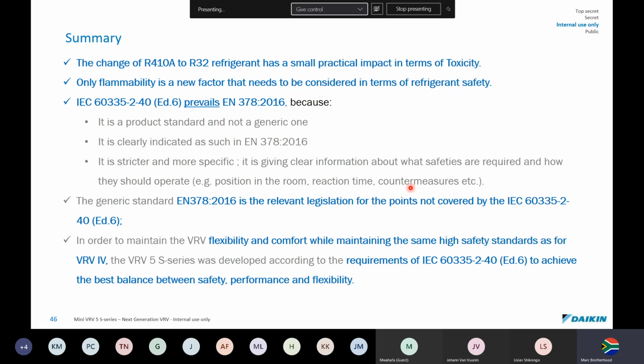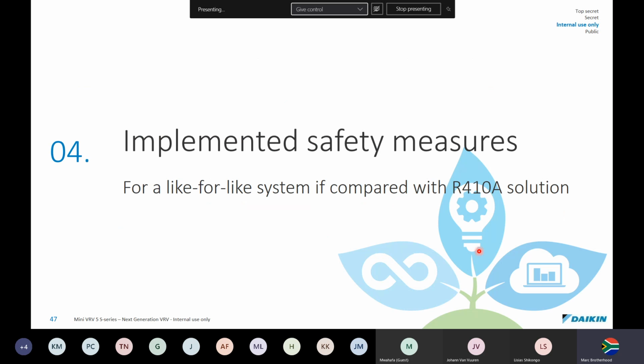Daikin use IEC standard 60335 because it's a lot stricter than 378. And in order to maintain the VRV flexibility and comfort while maintaining the same high safety standards as for VRV4, the VRV5 series was developed to the requirements of these standards. So they like to sort of brag about the standards that they've added. Importantly, because there's flammability and toxicity, we have had to implement safety measures.